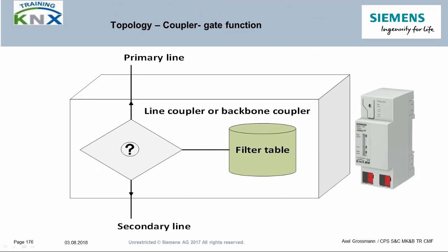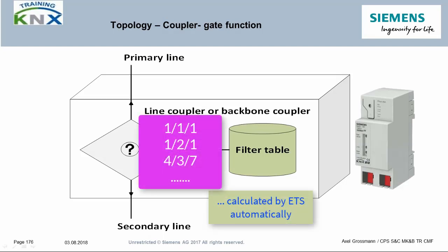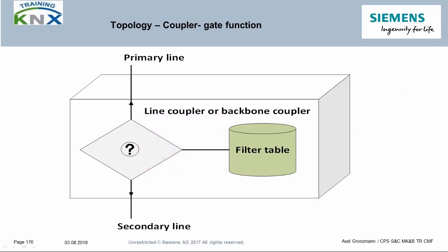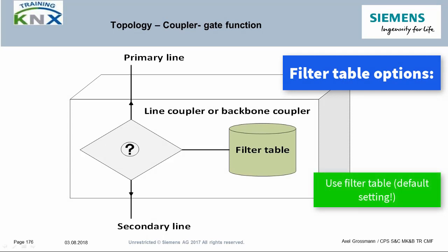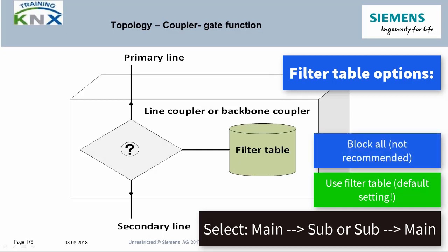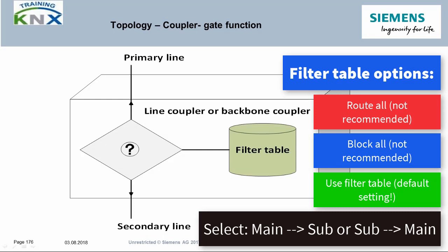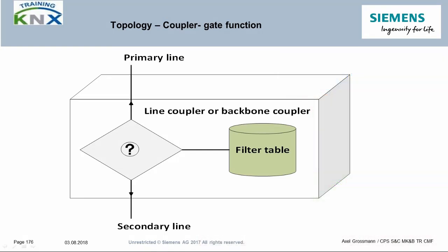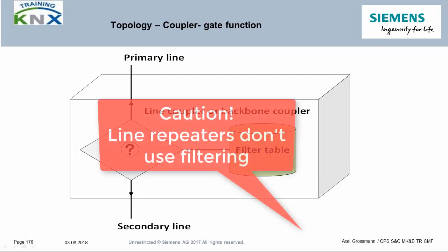The filter table of the couplers — more precisely the line and area couplers — is automatically calculated by ETS during the creation of address links between the communication objects. The project engineer can also use various parameters to determine whether group telegrams are only forwarded in one of the two directions, whether they are generally blocked or generally forwarded. It should be emphasized that couplers used as line repeaters do not have a filter table, because there was no need to optimize the possible threefold extension of the sublines with filter tables.